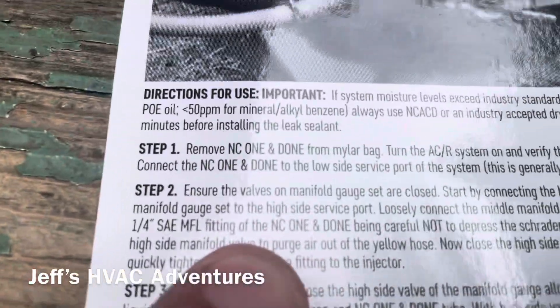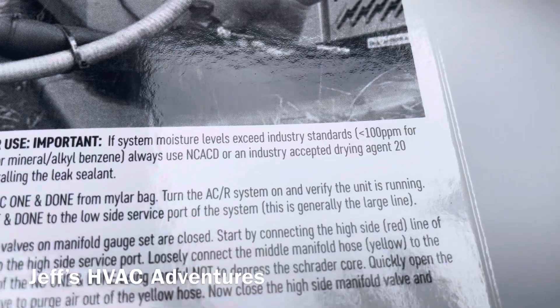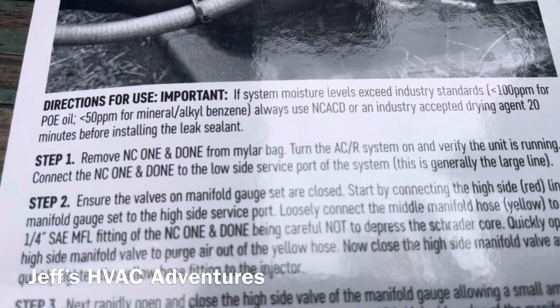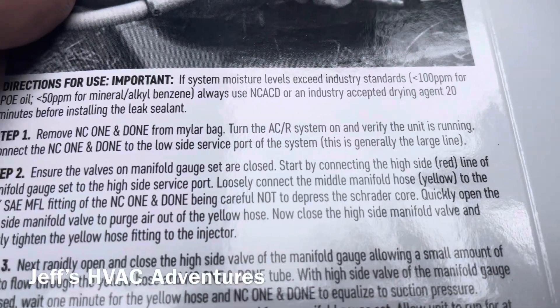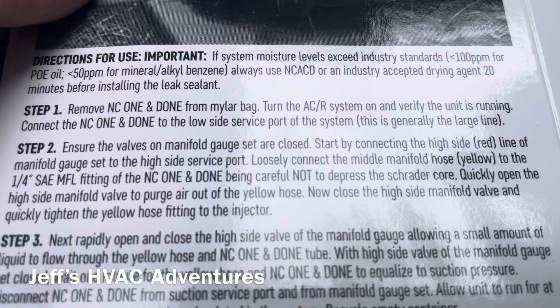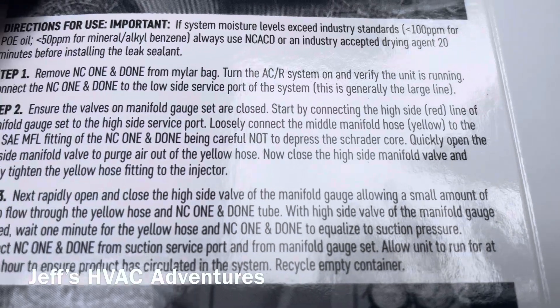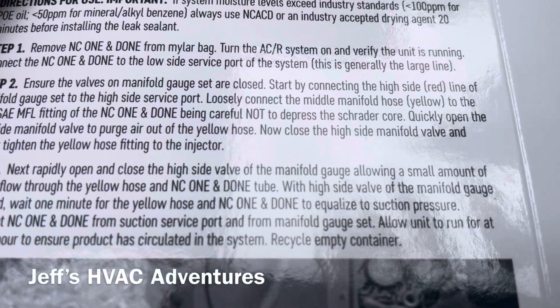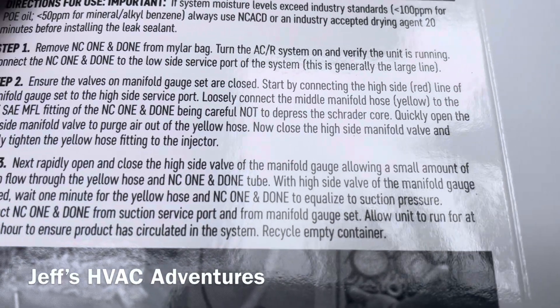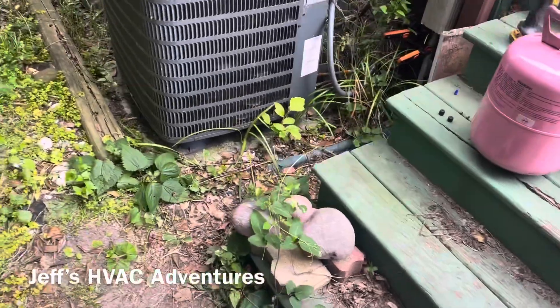Step two: ensure the valves on the manifold gauge set are closed. Connect the high-side line of the manifold gauge set to the high-side service port. Loosely connect the middle manifold hose to the quarter-inch fitting on the NC One and Done, being careful not to depress the Schrader core. Quickly open the high-side manifold valve to purge air out of the yellow hose, then close it and tighten the yellow hose fitting to the injector.